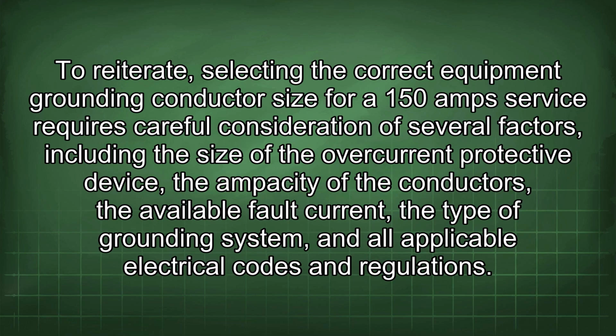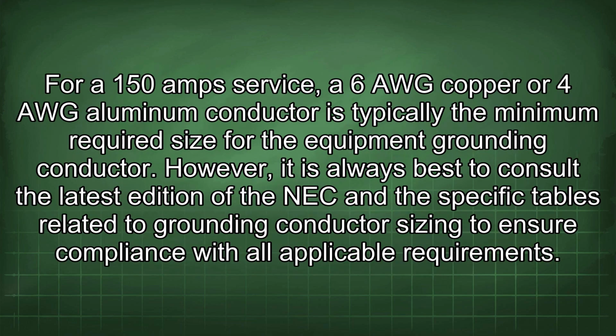This will help to ensure the safety of the electrical system and minimize the risk of electrical shock hazards and fire. To reiterate, selecting the correct equipment grounding conductor size for a 150 amp service requires careful consideration of several factors, including the size of the overcurrent protective device, the ampacity of the conductors, the available fault current, the type of grounding system, and all applicable electrical codes and regulations. For a 150 amp service, a 6 AWG copper or 4 AWG aluminum conductor is typically the minimum required size for the equipment grounding conductor.